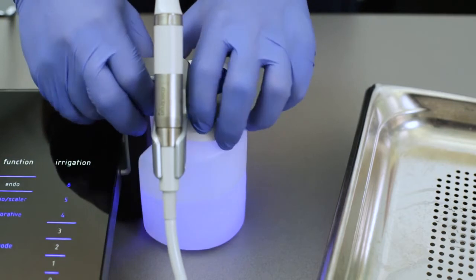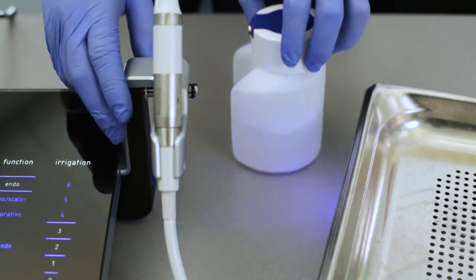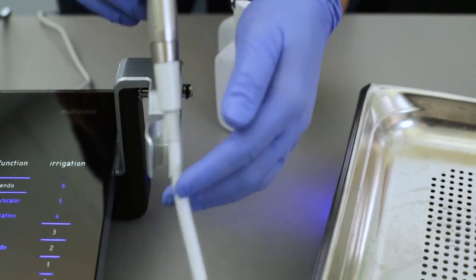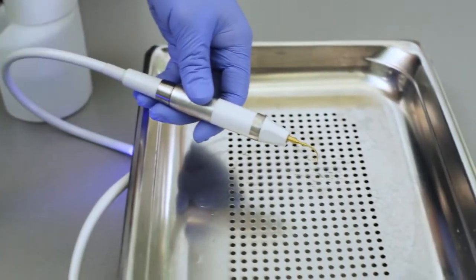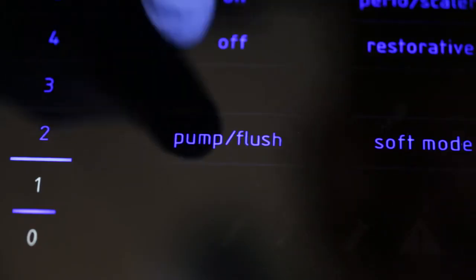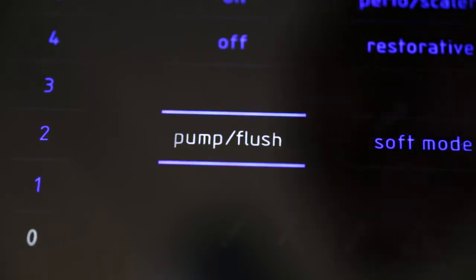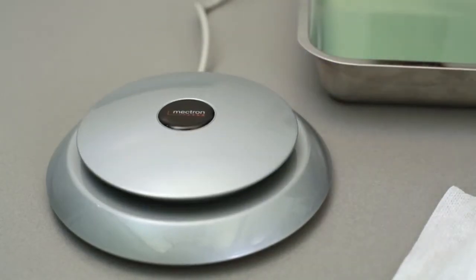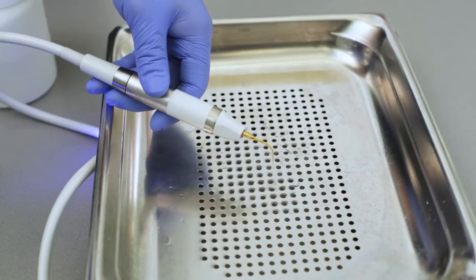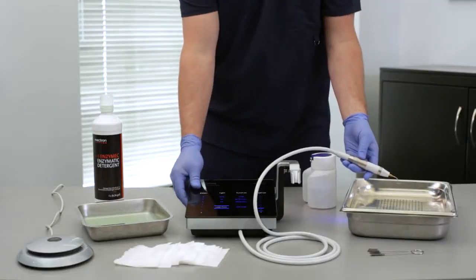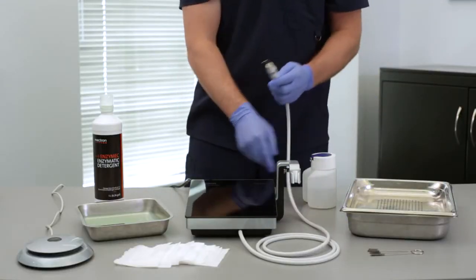First, disconnect the irrigation bottle from the device by pulling directly outward. Then aim the tip of the handpiece toward an area where it's okay to deploy liquid and run the pump flush function of the device. This will remove any residual irrigation solution from the irrigation line. Next, switch the device off.